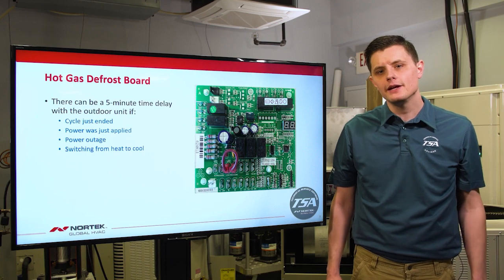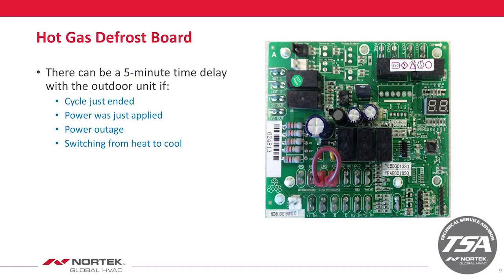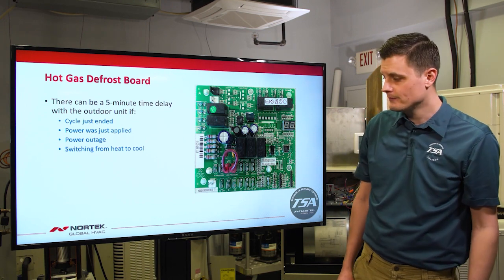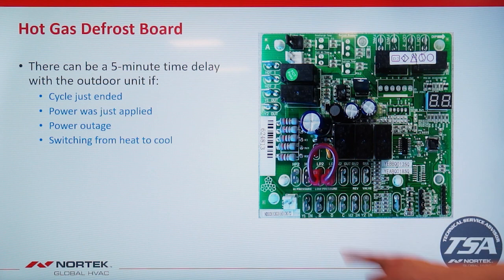There will be a five-minute time delay in the following situations: if a cycle just ended and you recall another heating or cooling cycle, you'll see an SC code. Also, if power was just applied on a new startup or after a power outage, you'll automatically have a five-minute time delay. Switching from heat pump mode to cooling mode will also give you a five-minute time delay. To bypass the short cycle timer during troubleshooting, jump the test pins for one second.